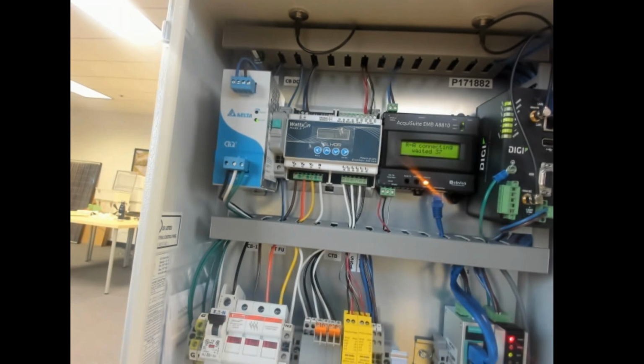If folks don't know the difference between a 5 amp CT and the Veris millivolt CTs, all you really need to know is the 5 amp CTs are a little bit more standard in higher amperage situations, especially utility scale projects, where the CTs aren't actually provided by Locus Energy but by the customer. We'll start to see and come across these a lot more.